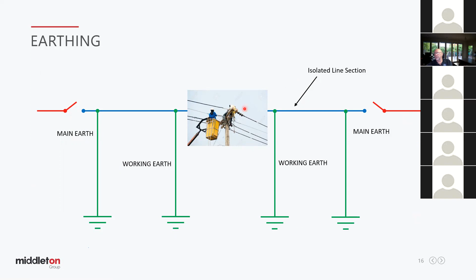Voltages could arise in the working location due to lightning, induction, broken conductors from other lines that cross. Now in the rail industry, quite often you've got other conductors that cross the rail corridor. So you may have a separate earth either side of potential falling conductor. That's normal, particularly on long sections of line. It's very important when you're putting up earth systems or earthing equipment that you keep track of them. Sometimes on the switching sheet, sometimes another way, but it's often said you count the earths out and you count them back in, so you've not left any on the system when you're finished. So that's the basic arrangement for earthing.